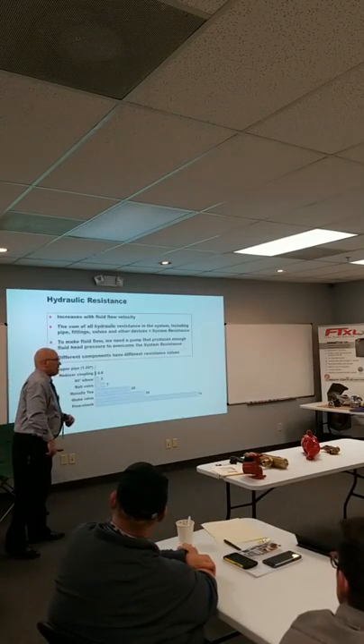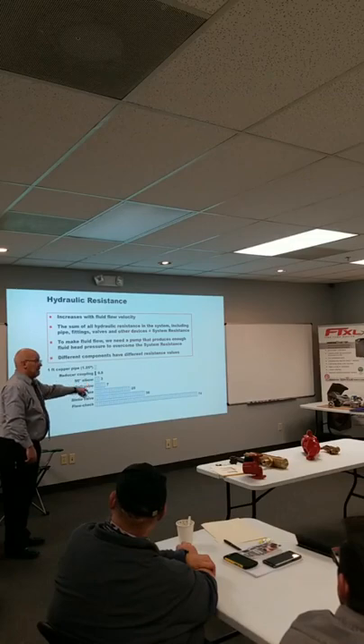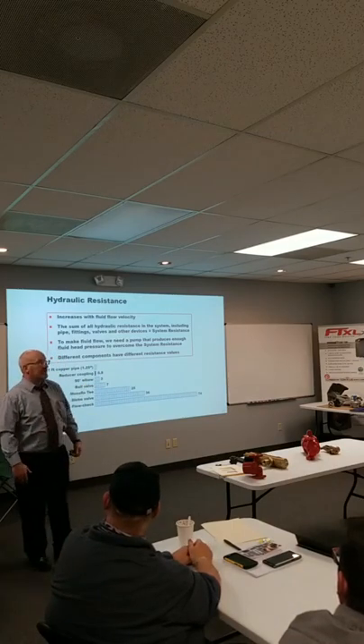Like, what was that globe valve? Why was that so high? Is that not a full flow globe valve? Look at a flow check. Talk about high. Ball valve, 7. Is that if you have a full flow? It's full port. So in heating, it's still got a 7? Yeah, that's 7. A little bit of 7 feet of piping worth of pressure drop. That's what that means. A full flow that you can see right through with the pipe still has a pressure drop.